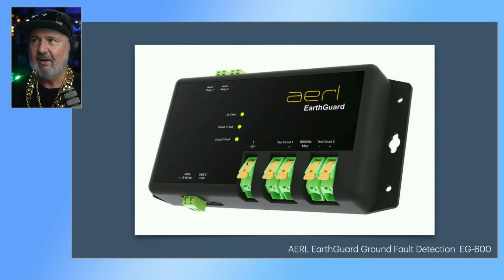But there you go. So adding an EarthGuard to, say for instance, that Victron MPPT would meet the requirements, because you can have an external device to provide that earth fault detection. However, that's about $700 as well. So the earth fault detection costs about the same as the MPPT. It's probably a good reason to look for products that actually have integrated earth fault detection, which, fun fact, AERL build into their charge controllers, so you don't have to buy the EarthGuard separately.